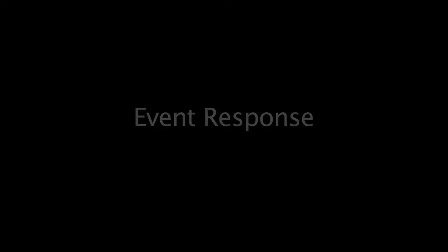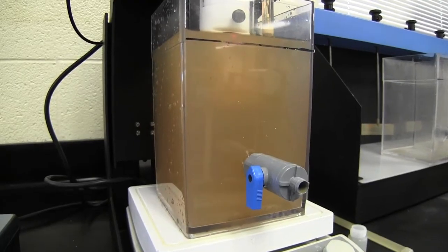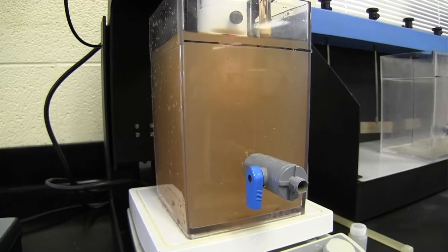With this technology, we can do things in a snap. Last year we dealt with a lot of drought; this year we've had a lot of rain. When we came in Monday morning, the turbidity was right around 40 and we were feeding about 28 parts. Within 30 minutes, the turbidity had jumped up to almost 400, so we ran the five-minute jar test and got 70 parts at that point. So we went from 28 to 70 parts in a matter of 30 minutes.